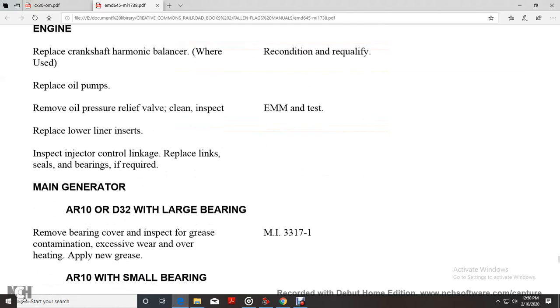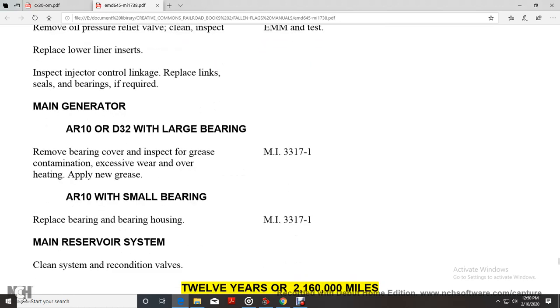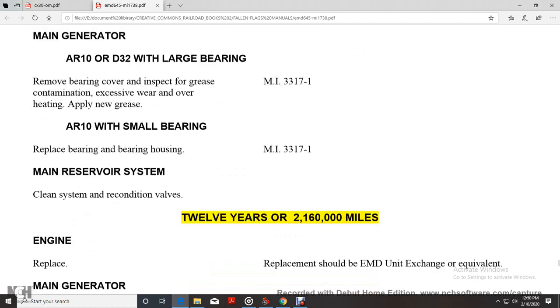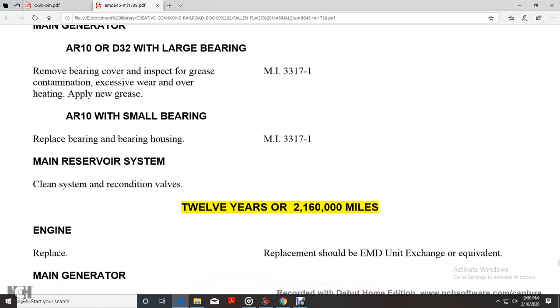Main generator AR10 or the D32 with a large bearing. Remove the bearing cover and inspect for grease contamination, excessive wear, and overheating, and apply new grease according to maintenance instruction 3317-1. AR10 with a small bearing, replace the bearing and bearing housing. Maintenance instruction 3317-1. Main Reservoir System, clean system, recondition valves. 12 years or 2,160,000 miles.